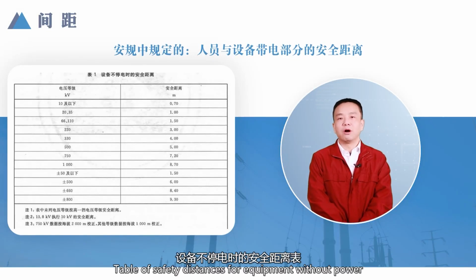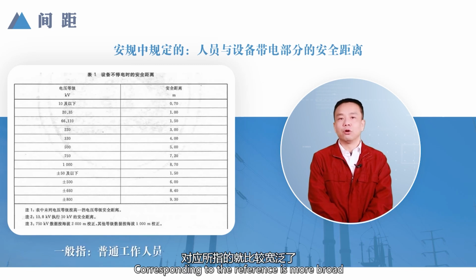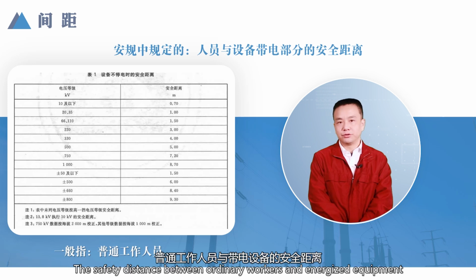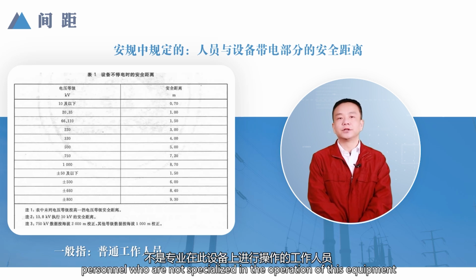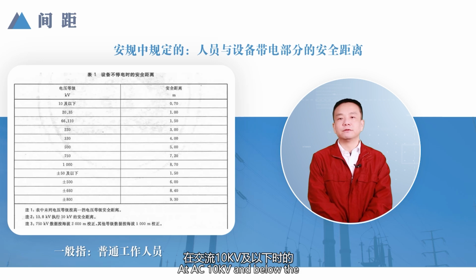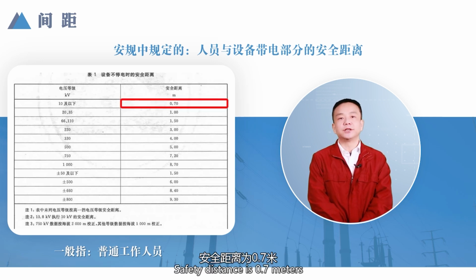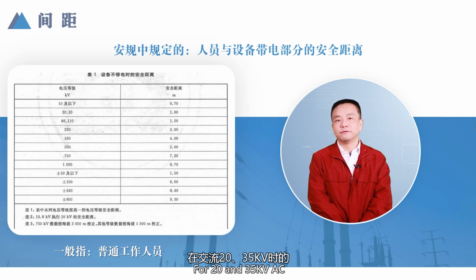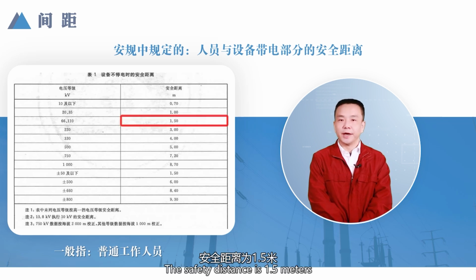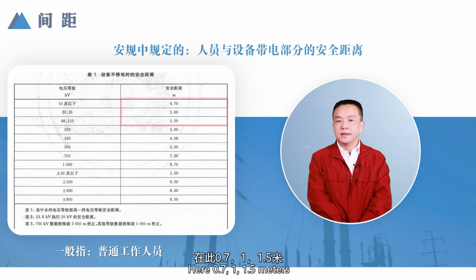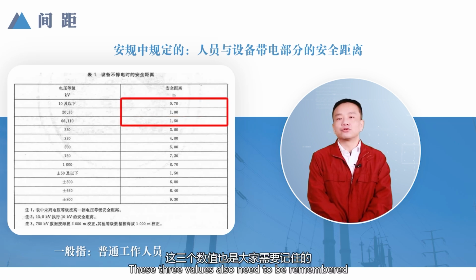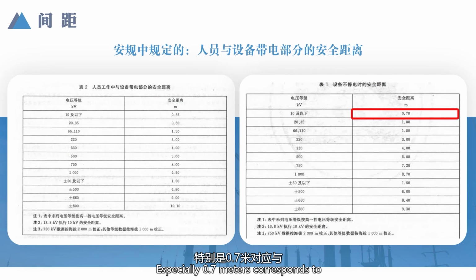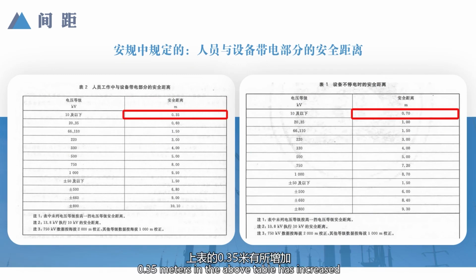The table of safety distances for equipment without power has a broader reference, and can be understood to mean the safety distance between ordinary workers and energized equipment, personnel who are not specialized in the operation of this equipment. At AC 10 kilovolts and below, the safety distance is 0.7 meters. For 20 and 35 kilovolts AC, the safety distance is 1 meter. At 66, 110 kilovolts AC, the safety distance is 1.5 meters. Here 0.7, 1, 1.5 meters. These 3 values also need to be remembered. Especially 0.7 meters, which has increased from 0.35 meters in the table above.